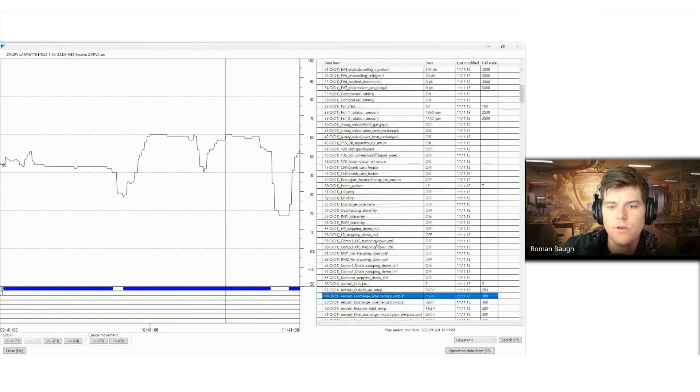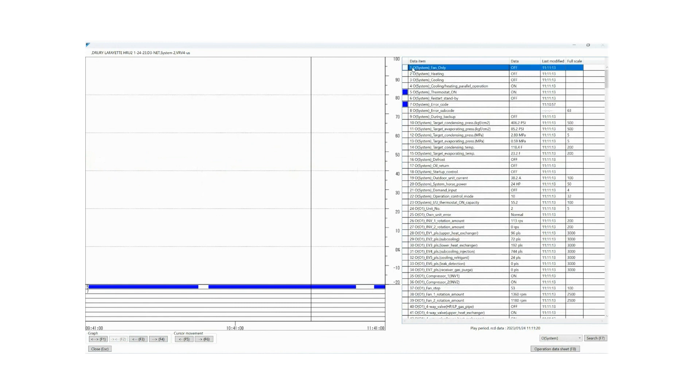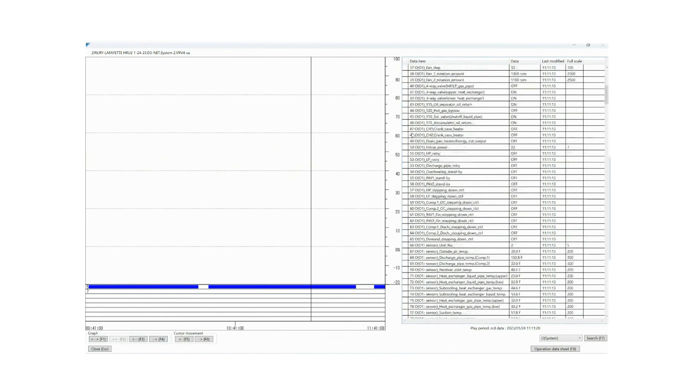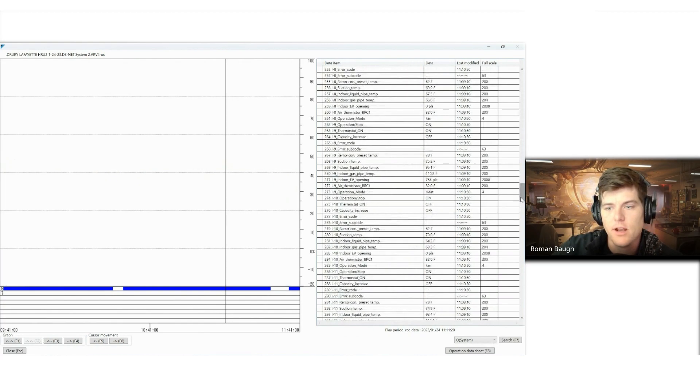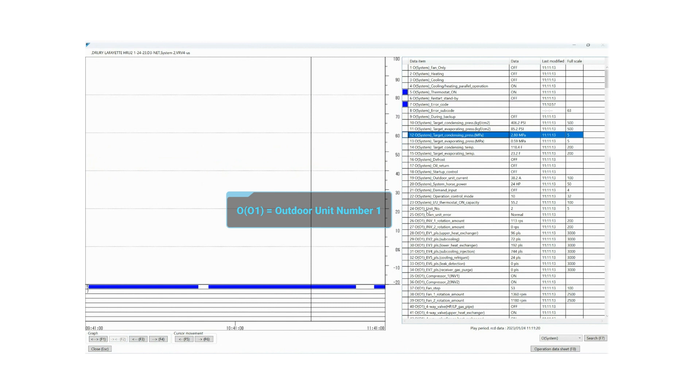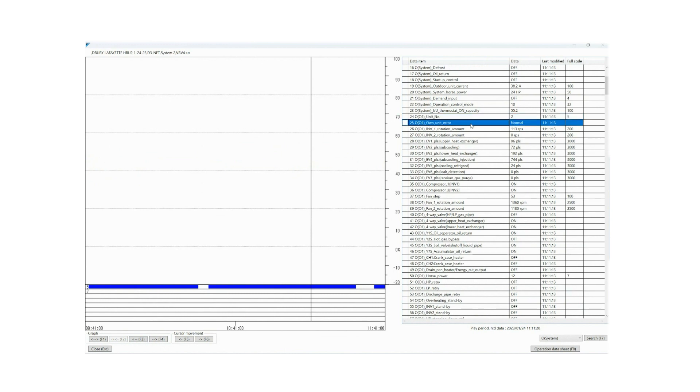So let's go through the majority of our data set here. You'll notice here the O, 1, 2, 3, 4. Every line item is numbered in service checker from top to bottom. That is how this program is set up. Those numbers don't really mean anything. They just help you to point out if you go to line item 152, that's what I'm looking at in service checker when you're troubleshooting or walking somebody else through it. Now the O is for outdoor. System, this is meaning that this is actually your system's set points. These are the things that my system programming is looking at. It's not until we get down here to where it says O and then O1 in parentheses that this tells me that now I'm looking at my outdoor unit number one data points. These are all the points that are being pulled in to my unit from my main control board that are plugged into my main control board.